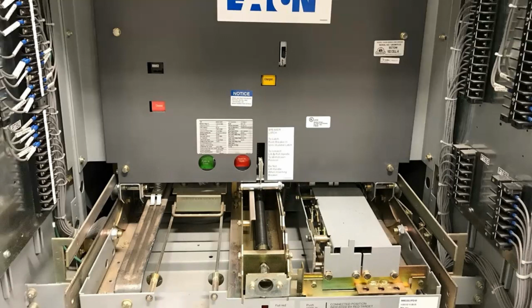So you've literally got to sit there and mechanically push up and down on these breakers, and you're tightening a spring, and then when you flip the thing on, it slams forward and makes an instant connection. And the reason for that is if a person real slowly flipped the breaker up and you've got 14,000 volts going to it, you're going to have a real big arcing issue. So that's kind of some of the things that we're talking about that's different in switchboards. A little bit more complex, a lot more expensive.